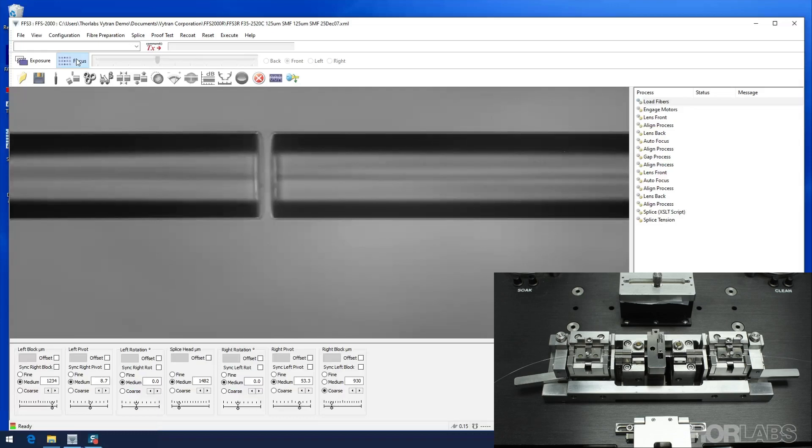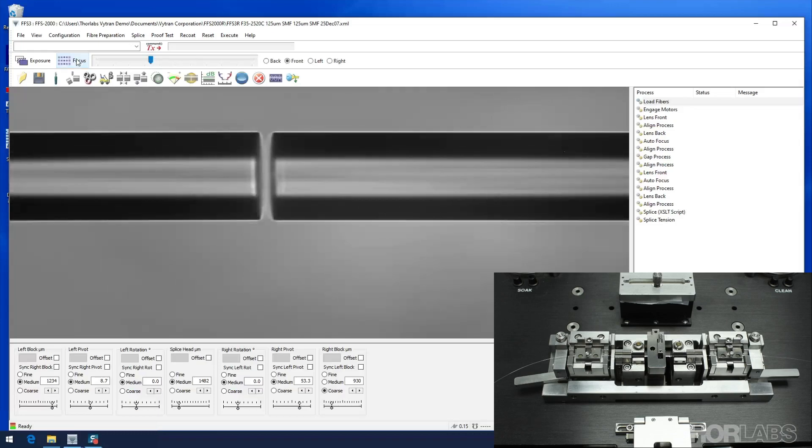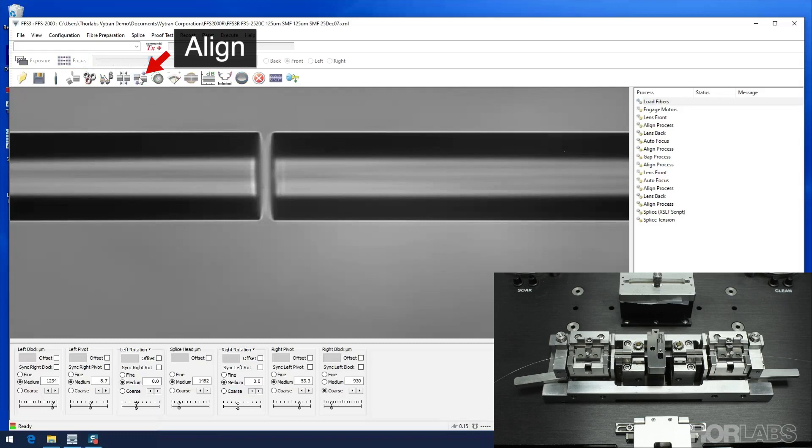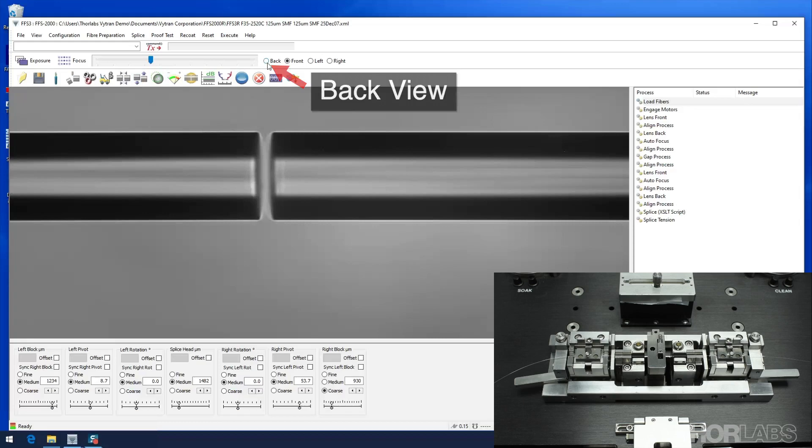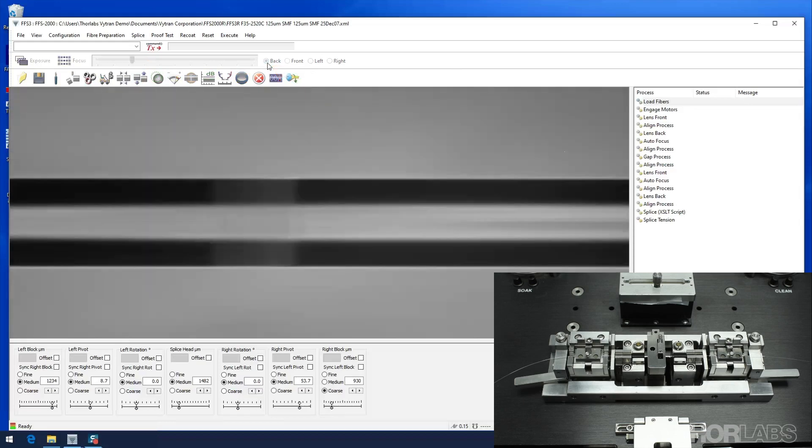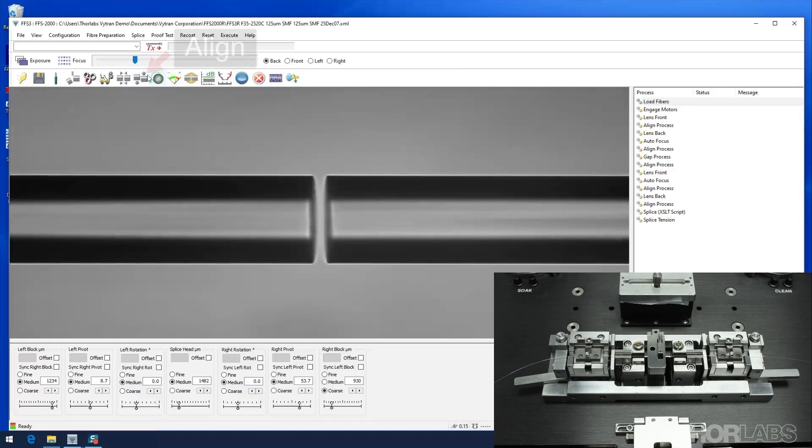Now both fibers should be on the fiber line and in good focus in both the front and back views. Now return to back view and align one final time. It is normal for the screen to go dark while switching views.